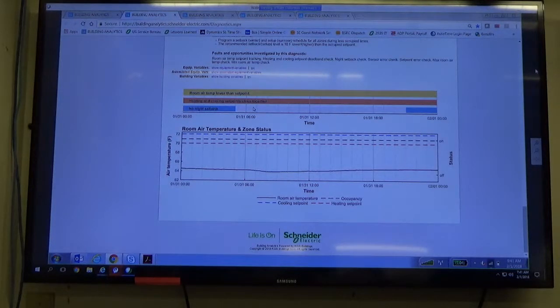Quick question: a lot of the flags we're getting on the temperature differentials are because we have adjustable thermostats in some of the spaces, and when staff changes those temperatures, they'll move it 4 or 5 degrees, and then we get the low temp alarm or high temp alarm because they've changed them. Is there a way, when the local set points have been changed, that it can identify that and not give us a flag, maybe with a time delay?